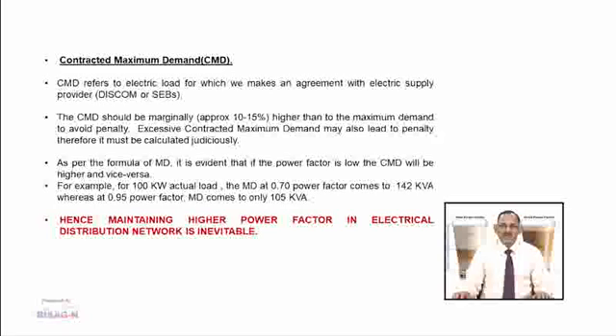For example, for a 100 kW actual load, the maximum demand at 0.70 power factor comes to 142 kVA, whereas at 0.95 power factor the MD comes to only 105 kVA. Hence, maintaining a higher power factor in the electrical distribution network is inevitable.